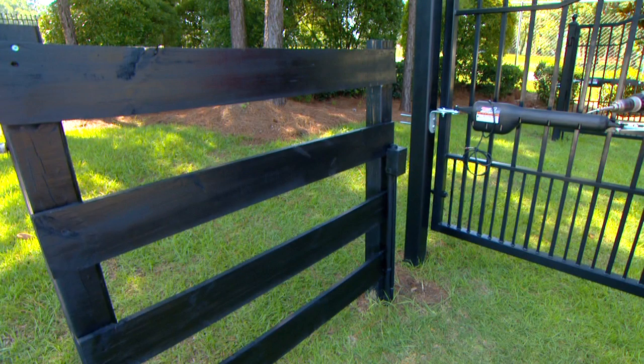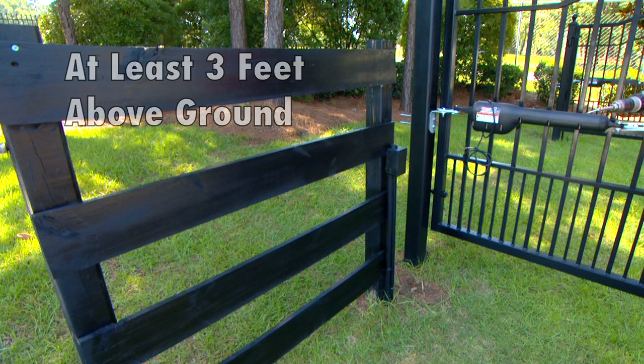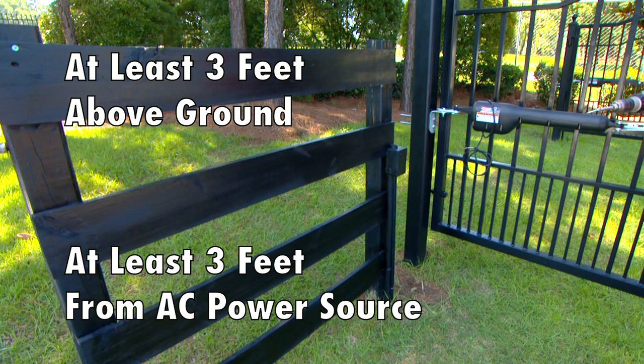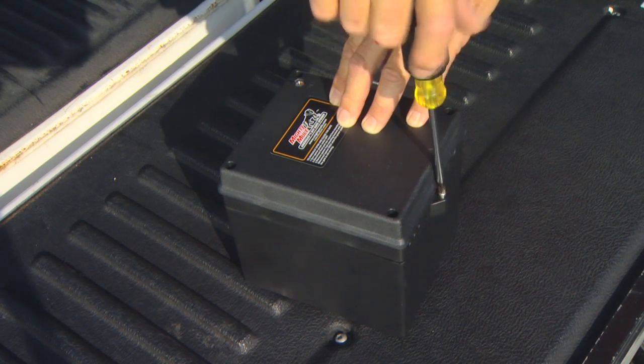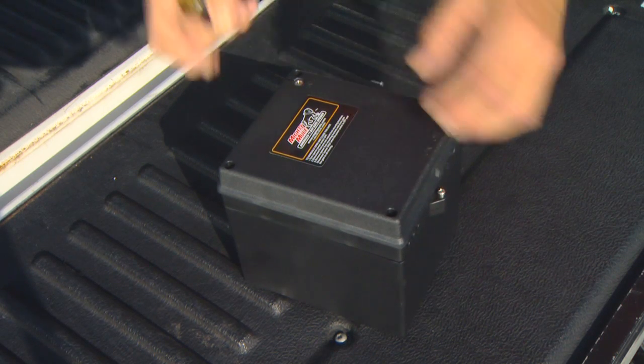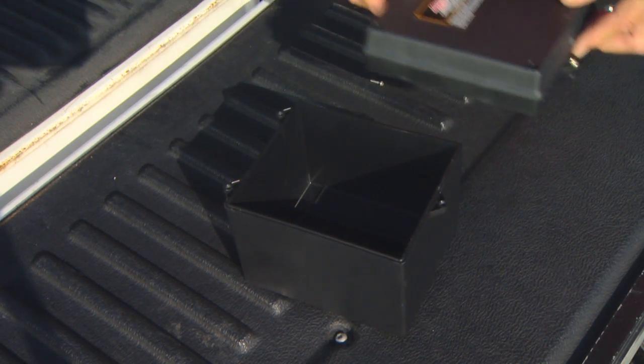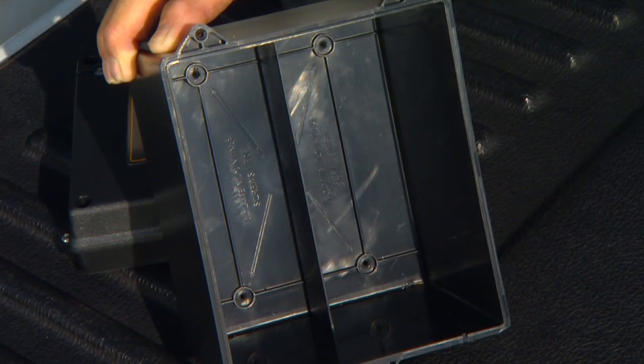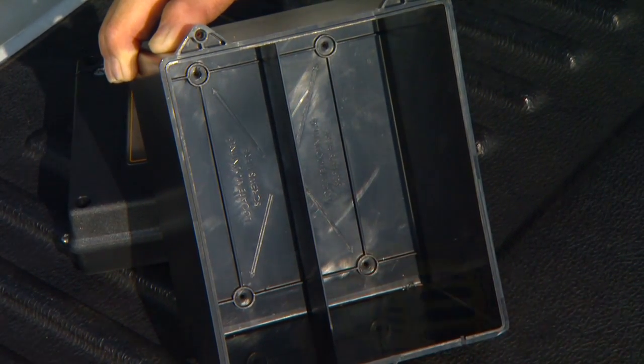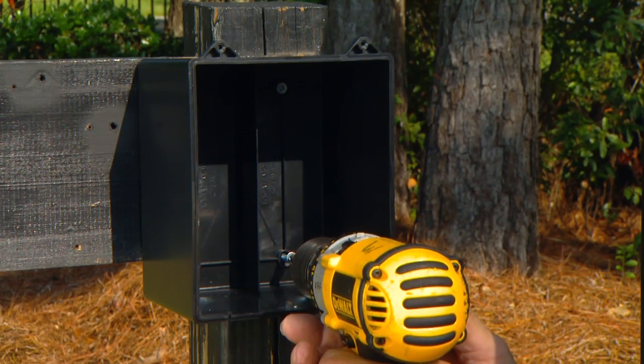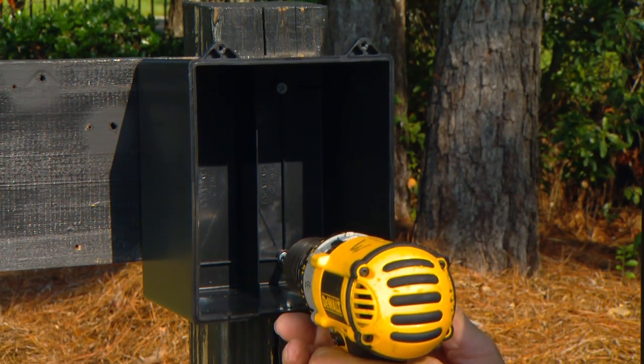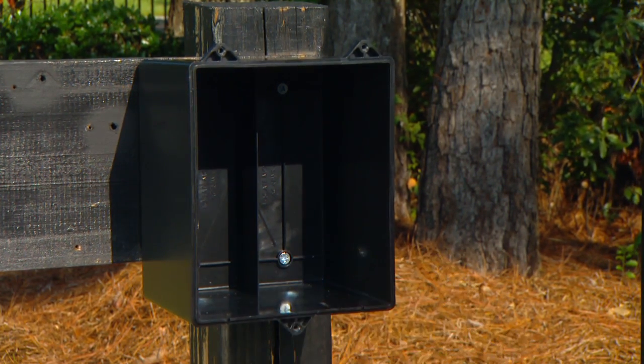The battery box and control box must be mounted at least 3 feet above the ground to protect it from rain splash and snow, and at least 3 feet away from an AC power source to prevent electrical interference. Remove the 3 control box mounting screws to separate the control box from the battery box. Locate the screw placement diagram inside the battery box and drill holes large enough to accommodate the screws for mounting the battery box to a secure surface.